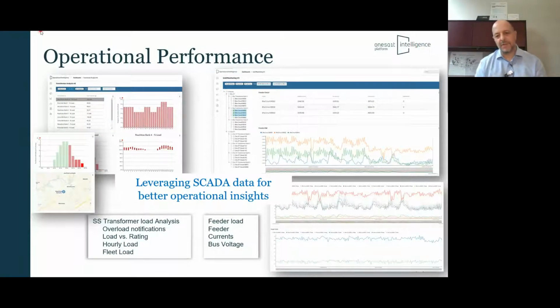Some of you have probably seen our demonstration of Onesait Intelligence and how we leverage SCADA data to improve operations, like better operational insight. We take data to analyze how substation transformers are doing, to notify about overloads and hourly load, understanding the fleet load across the entire number of transformers in the network. We also have a more traditional way of looking at voltage profiles, currents, and power factor, for example bus voltage across the network, coming from aggregated information at system level in terms of kWs, down to circuit level in terms of voltage, current, even current per phase or power factor. This is one of the use cases, probably the most immediate, like a very evolved historian, but also very important for aggregation of information.